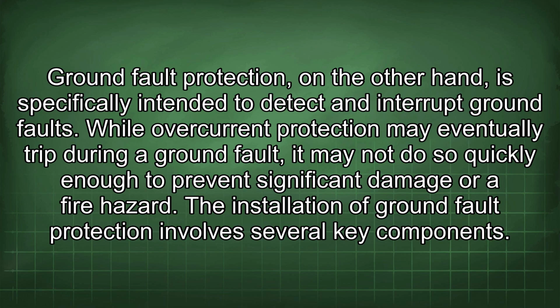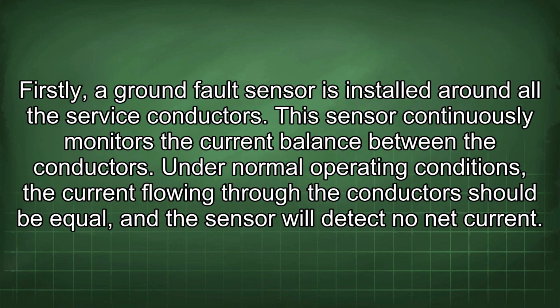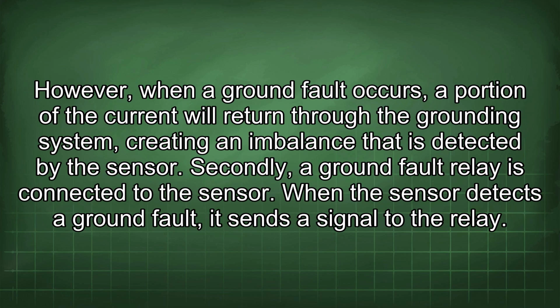The installation of ground fault protection involves several key components. Firstly, a ground fault sensor is installed around all the service conductors. This sensor continuously monitors the current balance between the conductors. Under normal operating conditions, the current flowing through the conductors should be equal, and the sensor will detect no net current. However, when a ground fault occurs, a portion of the current will return through the grounding system, creating an imbalance that is detected by the sensor.